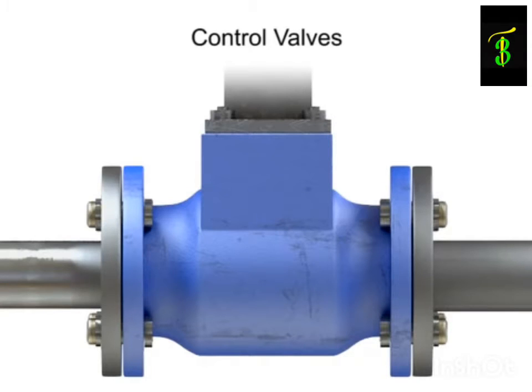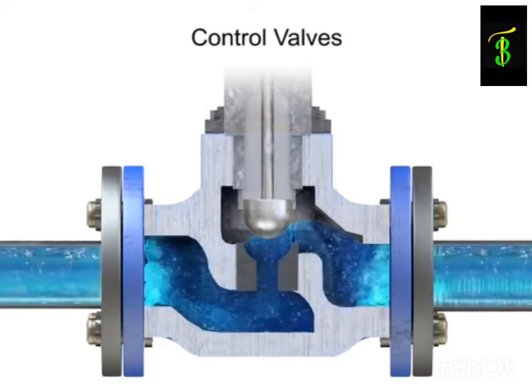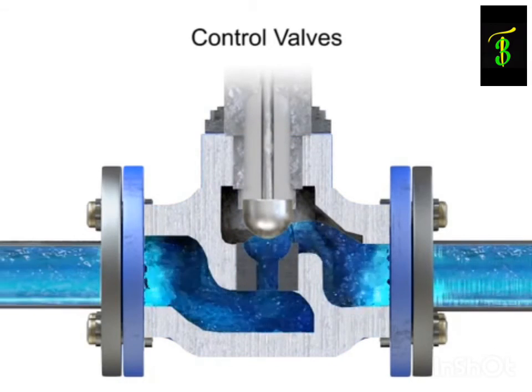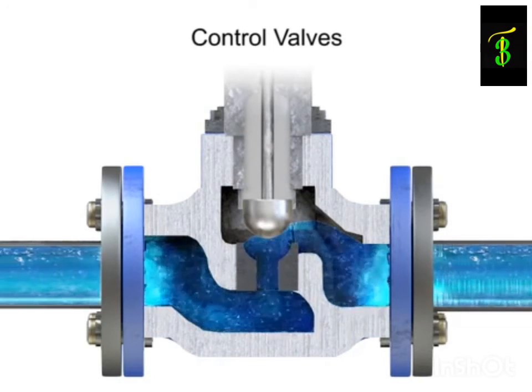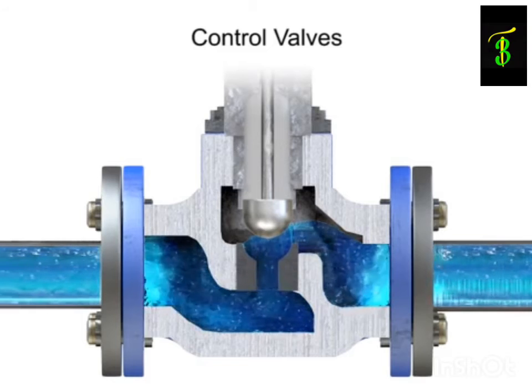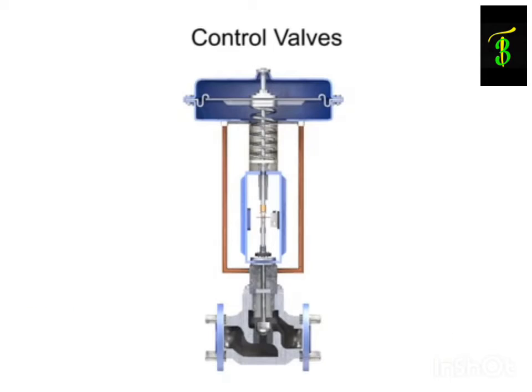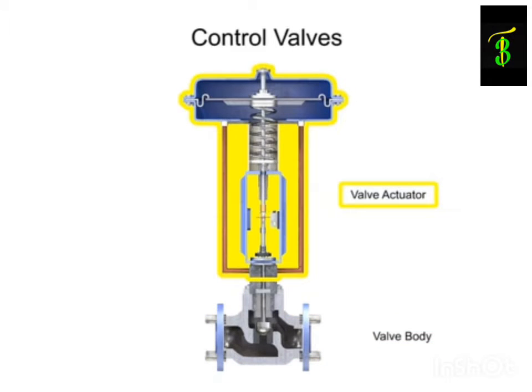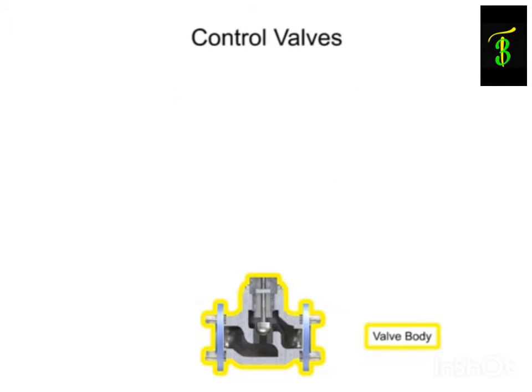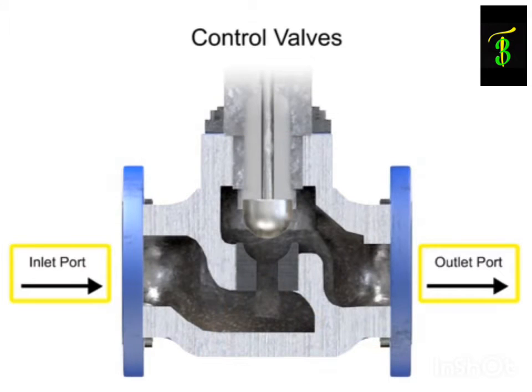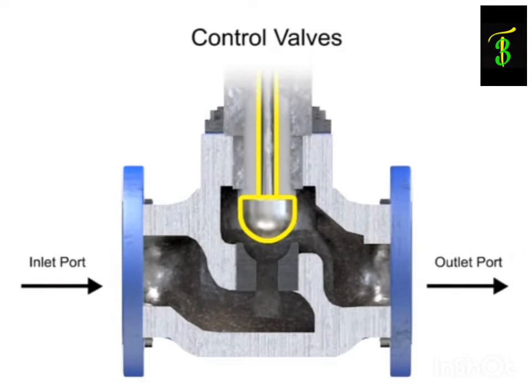Control valve actuators control fluid in a pipe by varying the orifice size through which the fluid flows. Control valves contain two major components: the valve body and the valve actuator. The valve body provides the fluid connections and a movable restrictor comprised of a valve stem and plug that is in contact with the fluid that varies the flow.